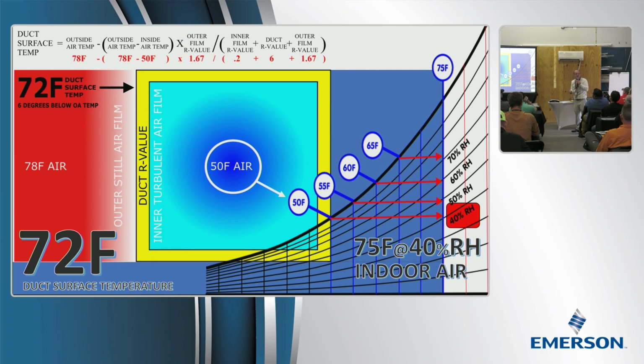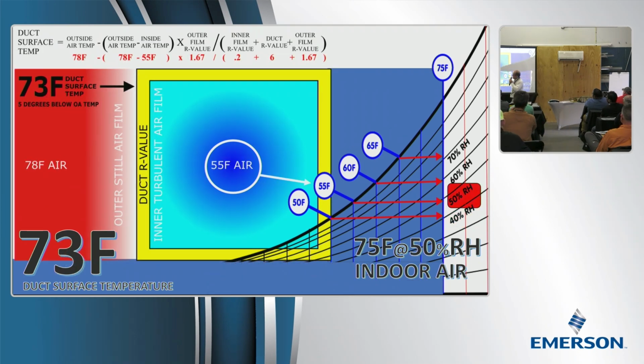Here's why I like cold air, and here's why cold air is not a malfunction. If you take air and you chill it down to 50 degrees, and in this case, we have a duct temperature of 72, so it could sweat, but the air will be reheated by the heat load, and it's going to be 40% relative humidity inside the home. Yeah, but the ducts sweat. Okay, well, speed it up. So we speed it up. Now we've got 73 degrees. It can still sweat, but the duct temperature went up 1 degree. Maybe it'll help, maybe it won't. We're still right at the dew point. But look what happened. Now we're only at 50% relative humidity.